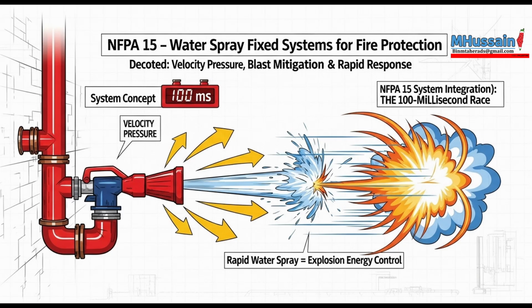It absolutely is. And this leads directly into the mandatory fire risk analysis required by 7.5.9. The 2022 edition made a really important update here. It explicitly forces the engineer to consider the potential for a vapor cloud explosion, or VCE. A VCE, that's a major hazard. Huge. And the risk analysis has to cover almost 20 different factors. 20 factors. Which ones usually end up being the trickiest design challenges? Often, it's things related to business continuity, continuity of operations, and just understanding the physical properties of the chemicals involved. Figuring out the probability and the potential scale of a VCE requires integrating complex models, gas dispersion, ignition sources, how confined the area is.